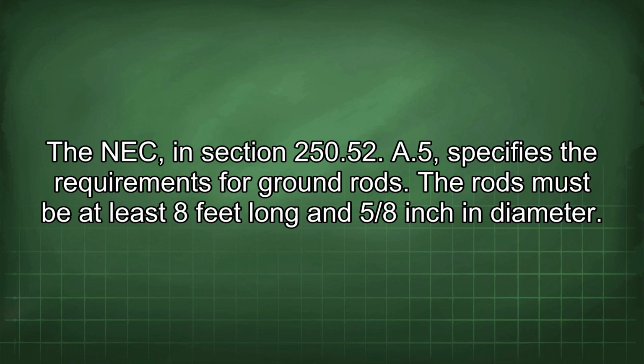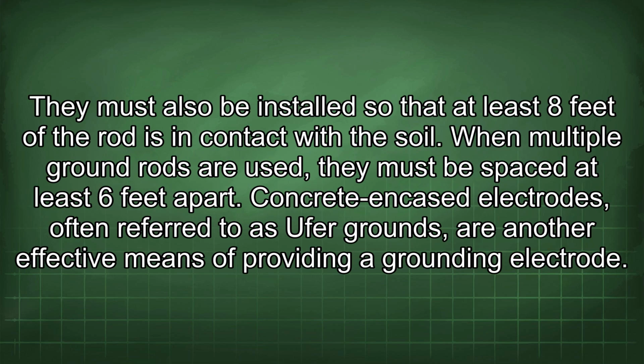The rods must be at least 8 feet long and 5/8 inch in diameter. They must also be installed so that at least 8 feet of the rod is in contact with the soil. When multiple ground rods are used, they must be spaced at least 6 feet apart. Concrete encased electrodes, often referred to as Ufer grounds, are another effective means of providing a grounding electrode.